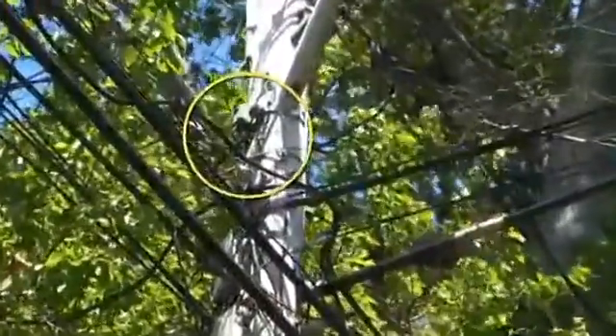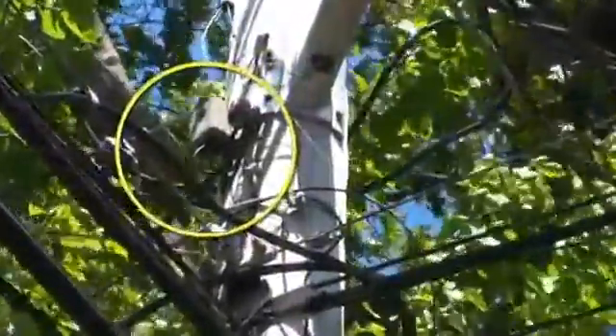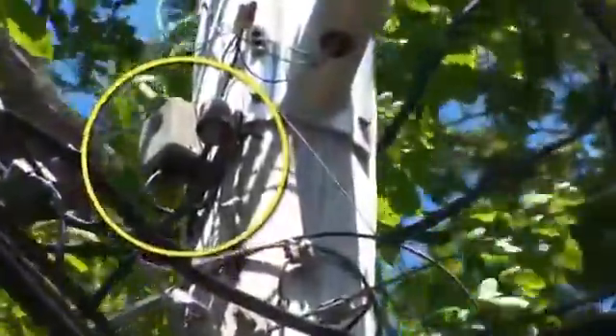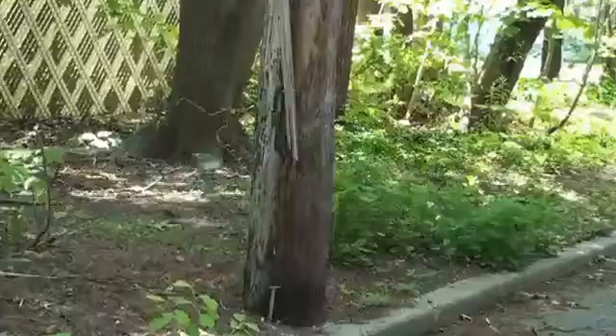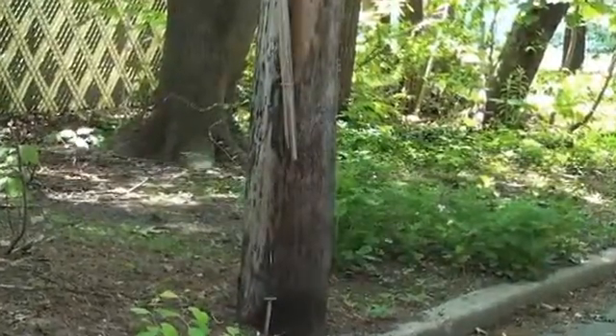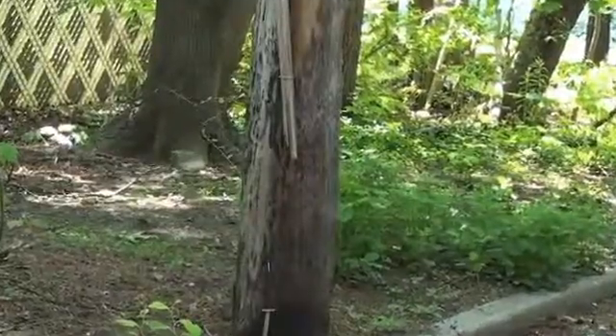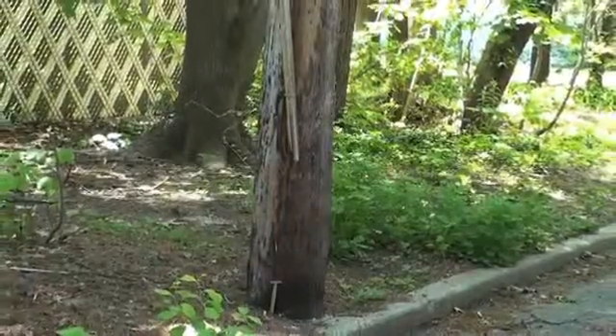Here, someone has placed a protector to splice out a drop wire and has put it too close to the streetlight bracket. Don't work on something like this. Refer it to your supervisor. On poles with an MGN, multi-grounded neutral wire, if it's missing or broken like it is here, inspect one transformer on either side of the pole you'll be working on. If you don't see an MGN, notify your supervisor. Even if there is an MGN in good condition, check it with your voltage detector before proceeding.